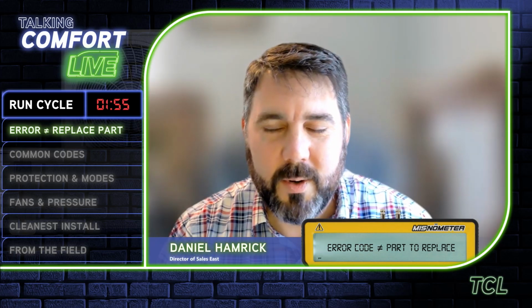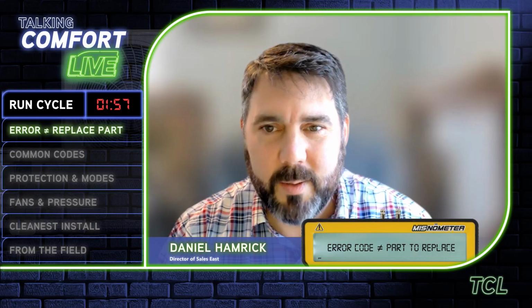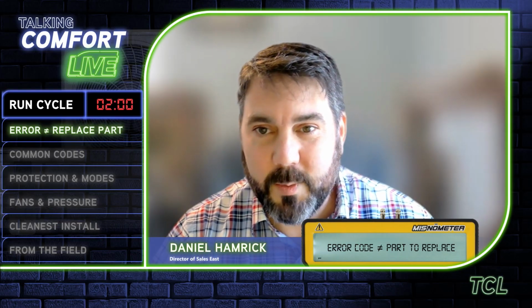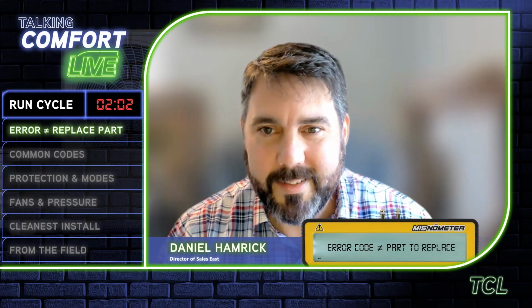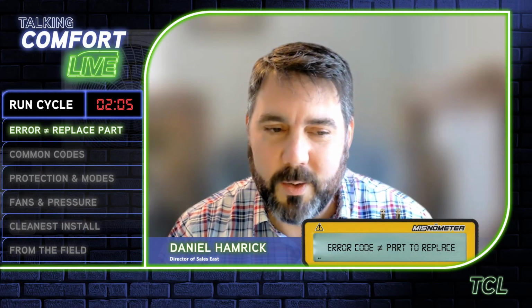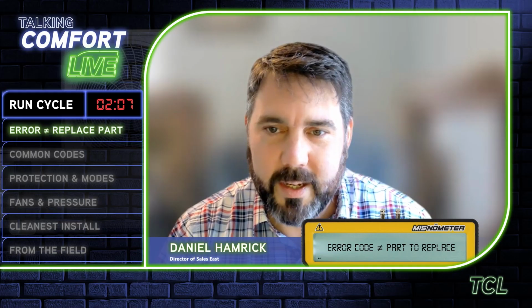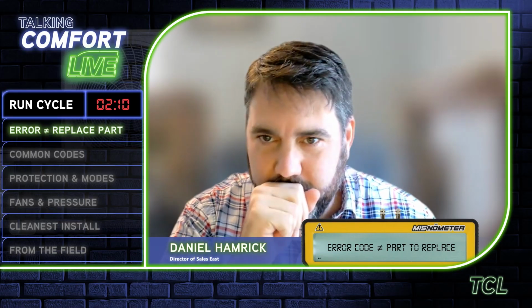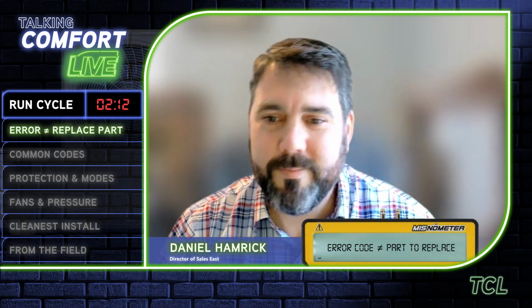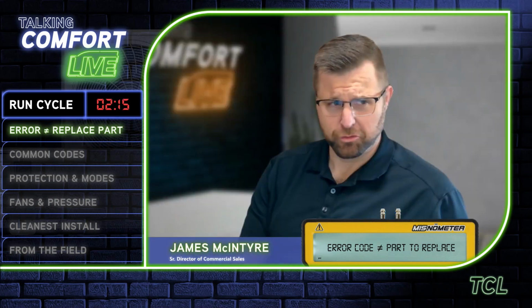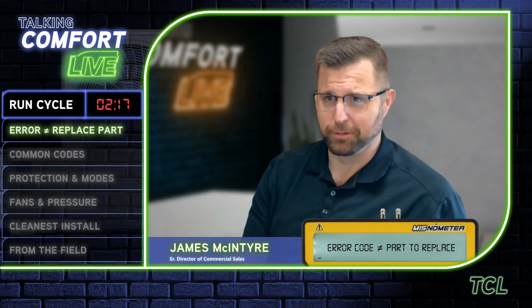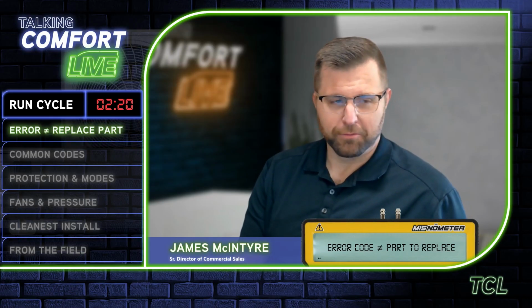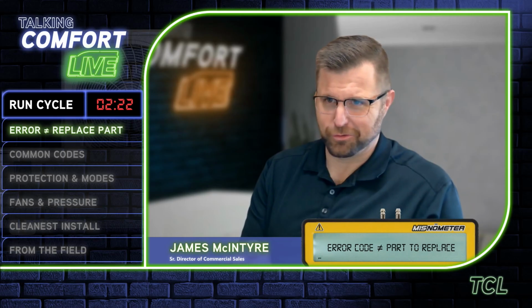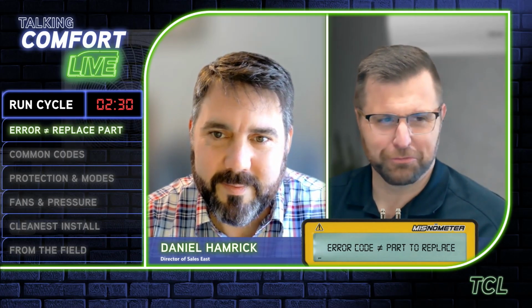I have tried one of those 120 to 230 volt step up transformers. Of course, it wasn't an expensive one, and the communication doesn't work well off of that. It'll throw a communication code immediately. We've seen that on display units. We're trying to have training carts they can plug into wherever, like the break room. I've seen that quite a bit. Also, even just trying to show people what the voltage might be doesn't work right. It won't match any of your troubleshooting charts, stuff like that.